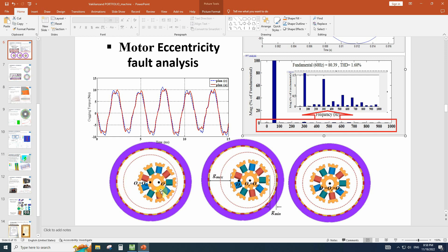On the other hand, in the dynamic eccentricity, the center of the rotation and center of the stator are the same, but the rotor part is eccentric. It means that the center of the rotor is not matched with the center of rotation.